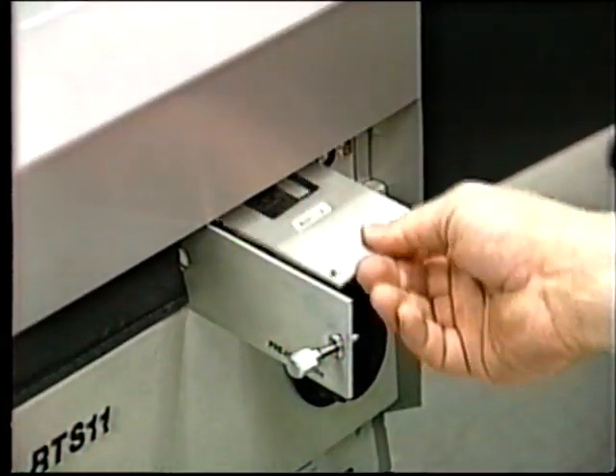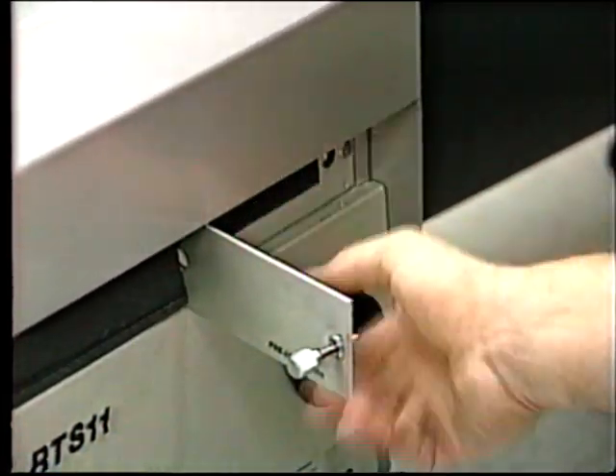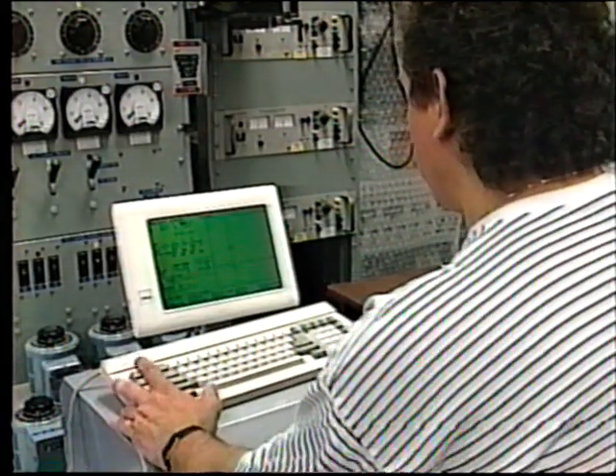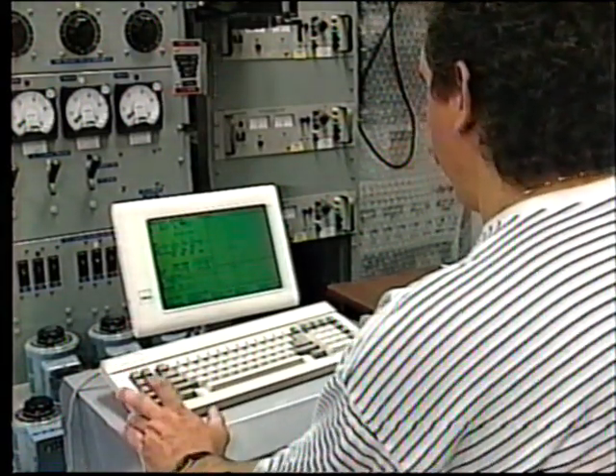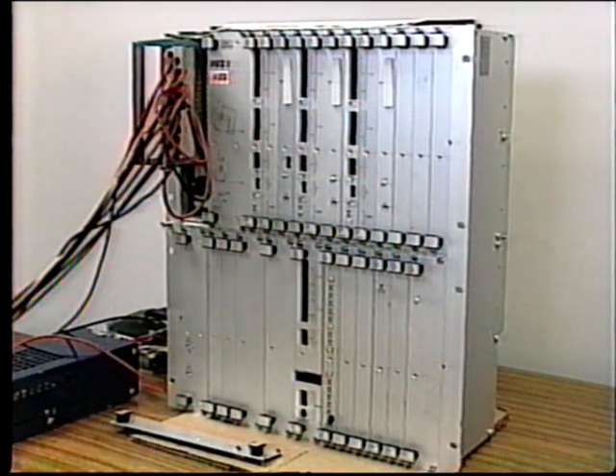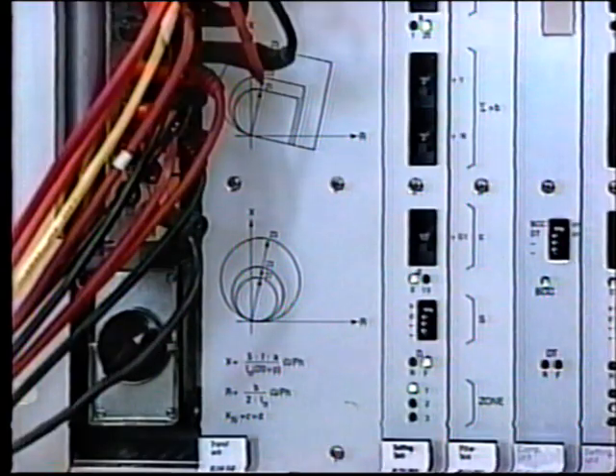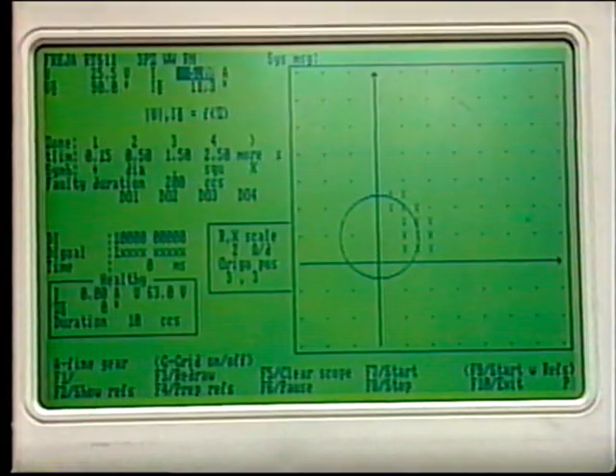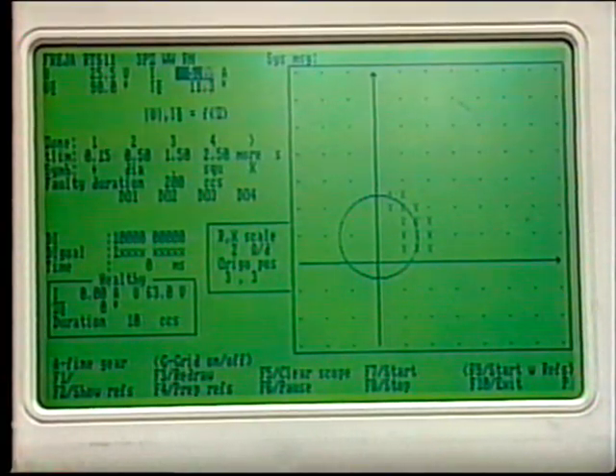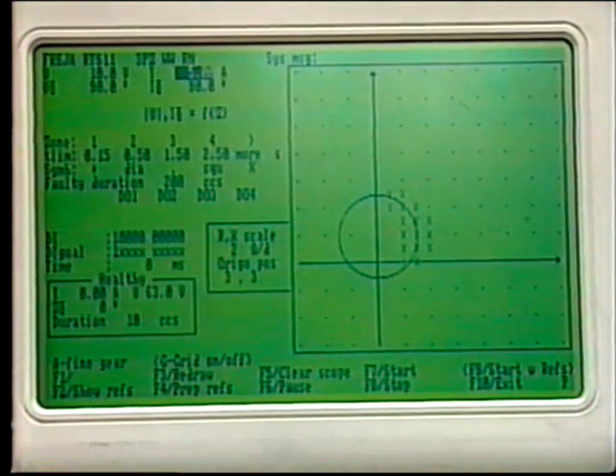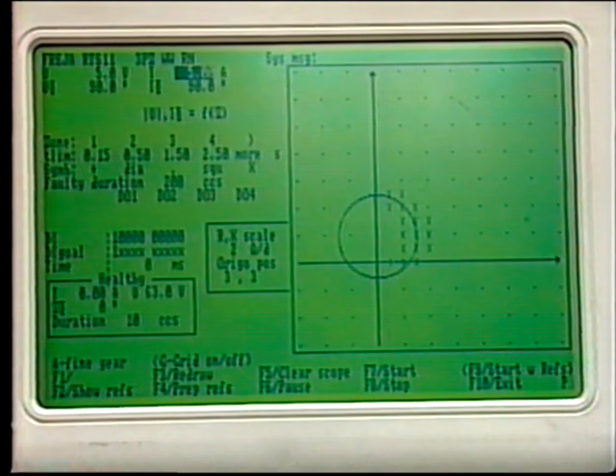Digital relays are usually tested by one of the recently developed test sets, which use microprocessor control. This type of test set applies simulated fault signals to the relay based on the physical parameters of the actual power circuit. Thus, the relay actually responds to perceived fault conditions. The test program for each different type of relay is stored in the computer. This results in a considerable saving of time, particularly with complex relays such as distance relays.